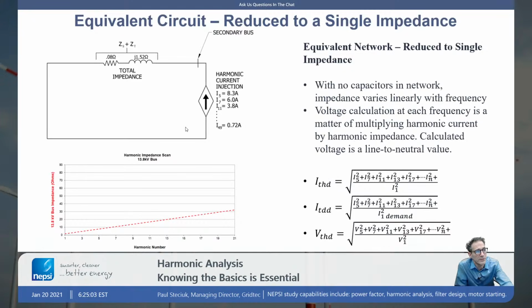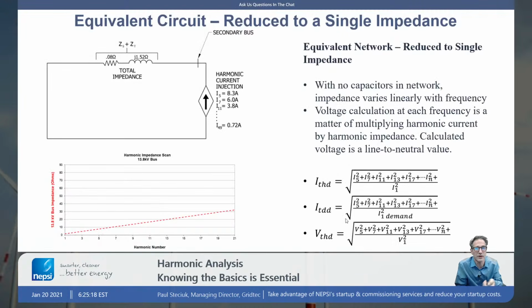So once we are able to calculate the voltage and current throughout this network, we can then calculate what's called the total harmonic current distortion here, and the total demand distortion, and then finally the total harmonic distortion. So ITHD, ITDD, and VTHD. The difference between THD and TDD is that demand distortion is based upon some demand period, normally 15 minutes. What is the maximum demand of a facility over a 15-minute period, and that becomes the denominator for the calculation.